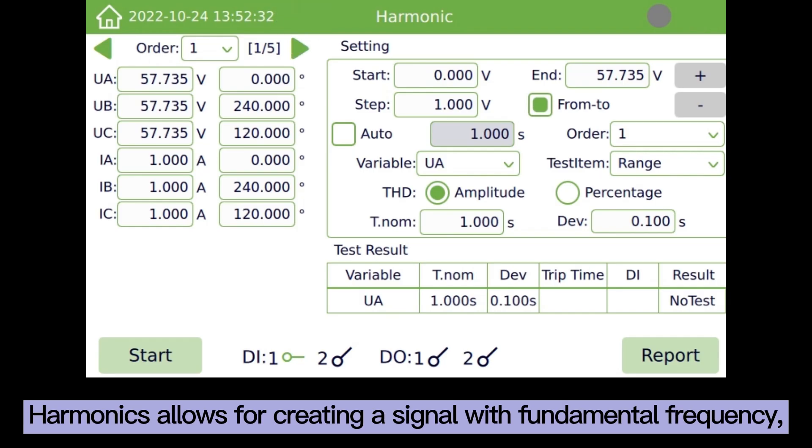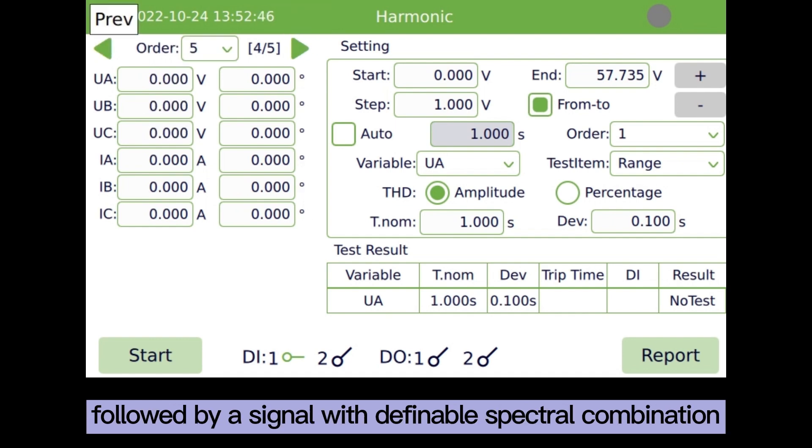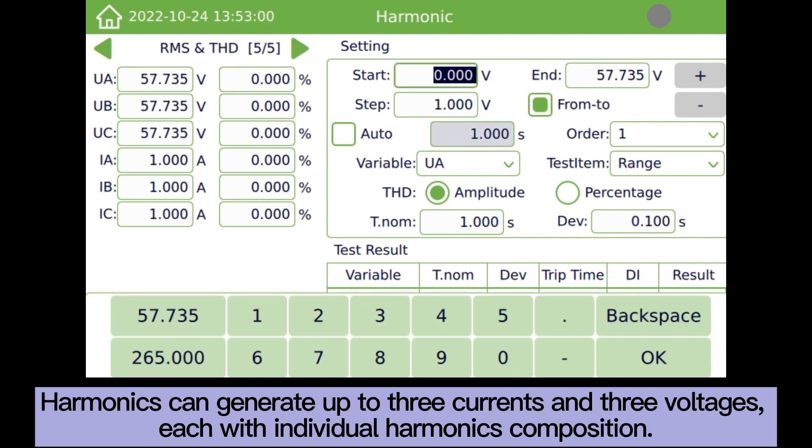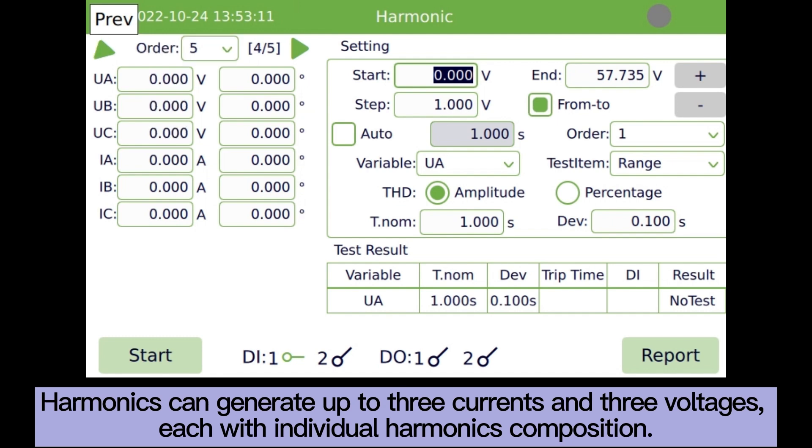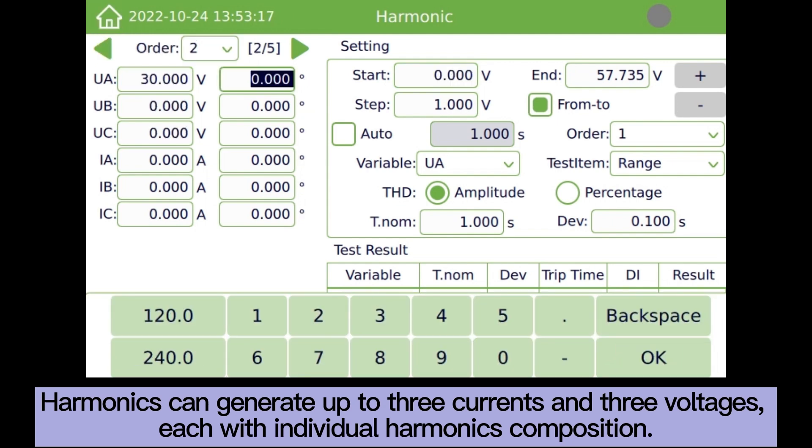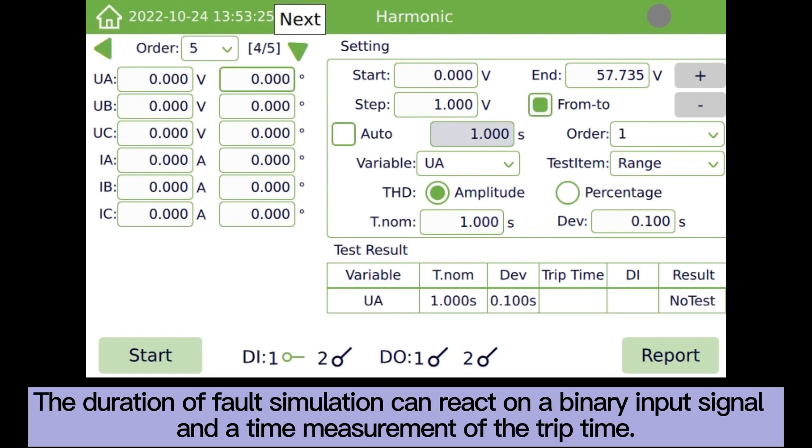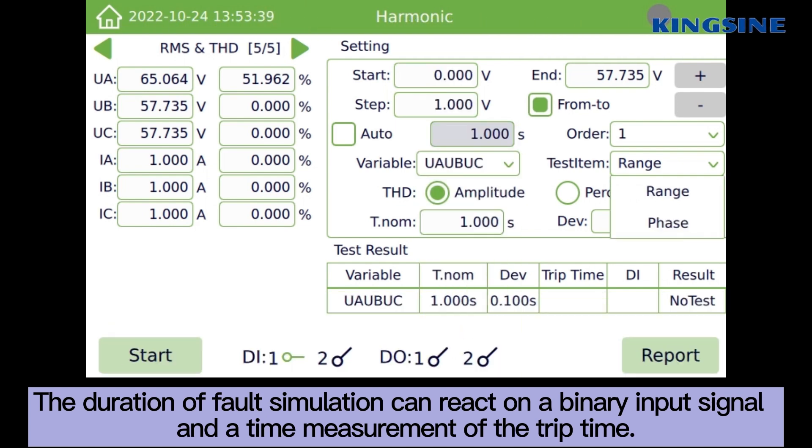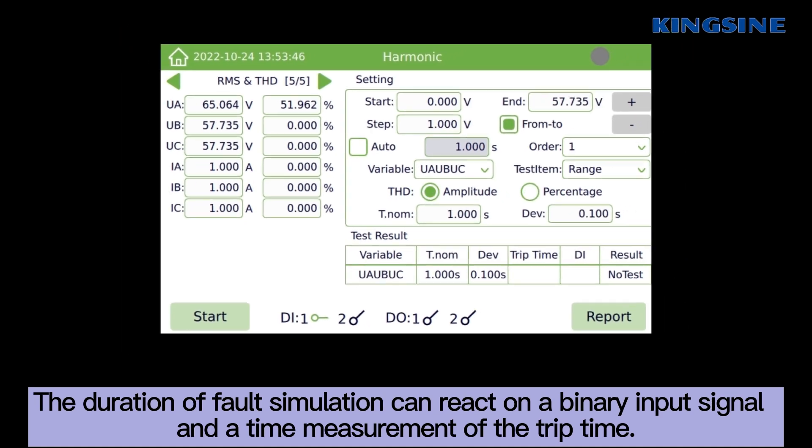Harmonics allows for creating a signal with fundamental frequency, followed by a signal with definable spectral combination. Harmonics can generate up to three currents and three voltages, each with the individual harmonics composition. The duration of fault simulation can react on a binary input signal, and a time measurement of the trip time.